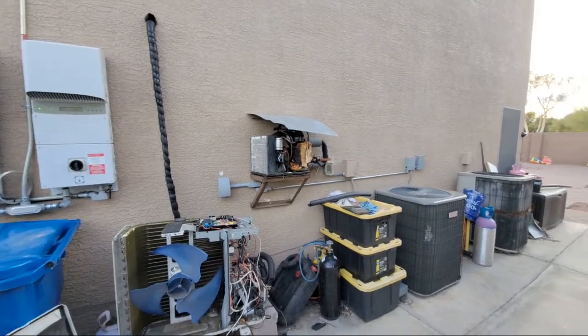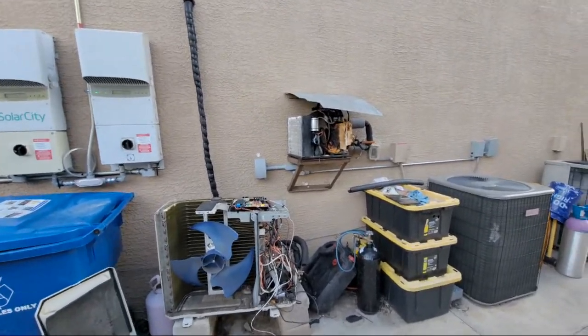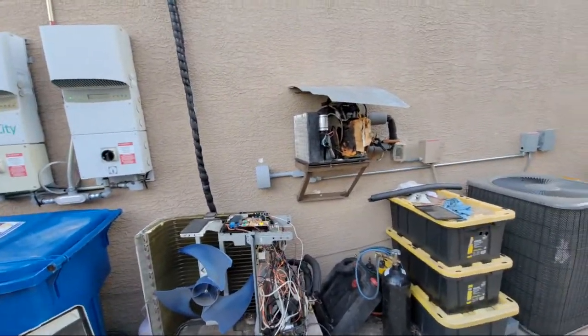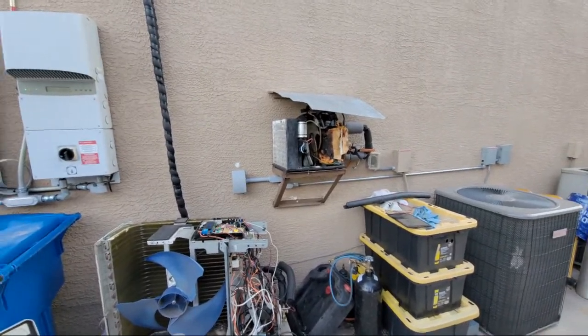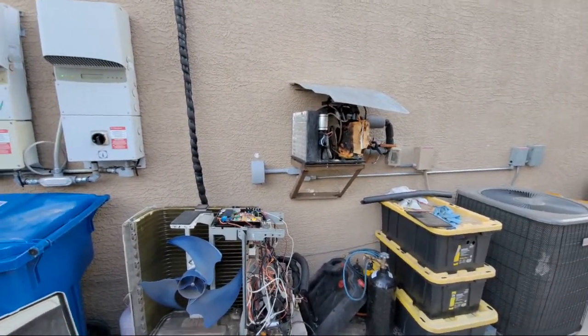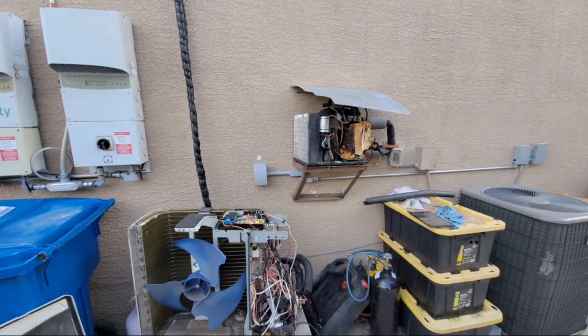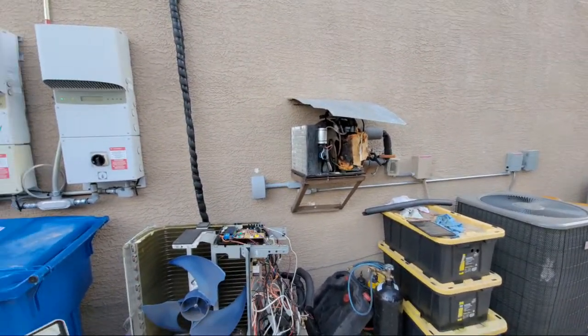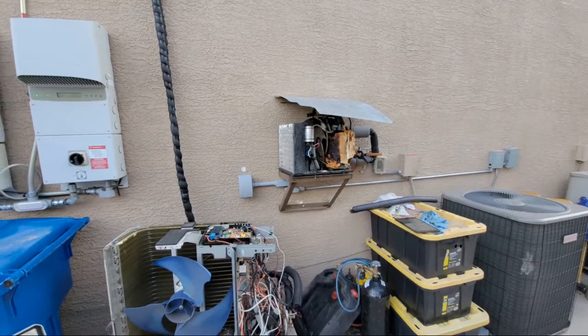That way that thing's just kept simple. It's just a heat pump for the water heater. And in the winter, we'll definitely keep it on the solar charger inverter and try to make it run off the sun as much as possible. In the winter, when this needs to run the most though, it's 50 degree supply water instead of 80 coming in.